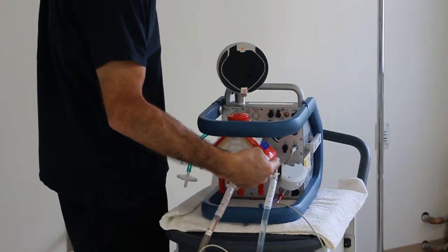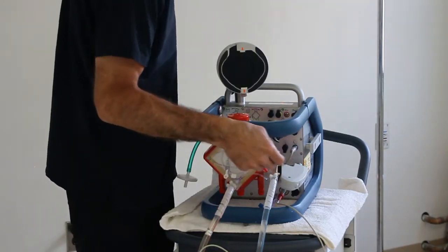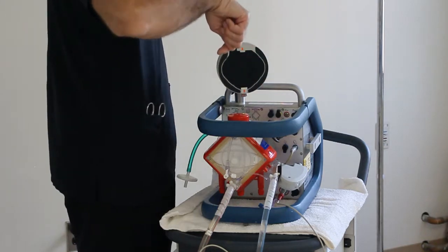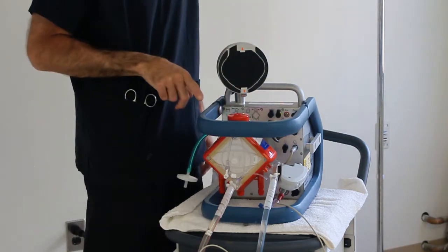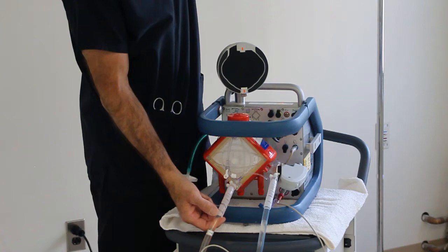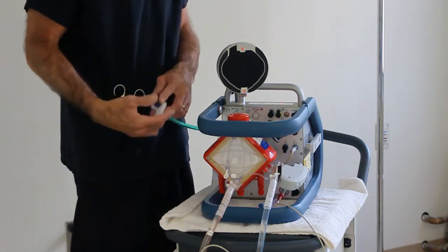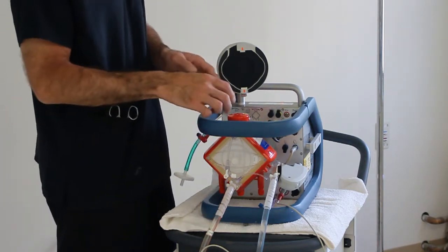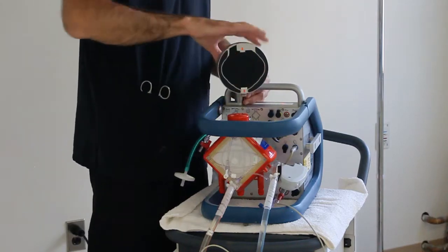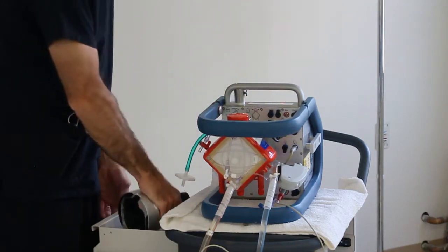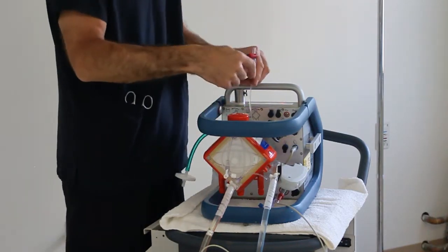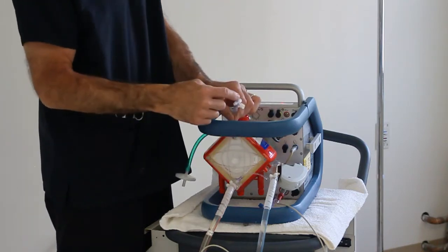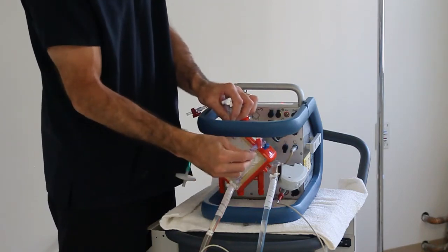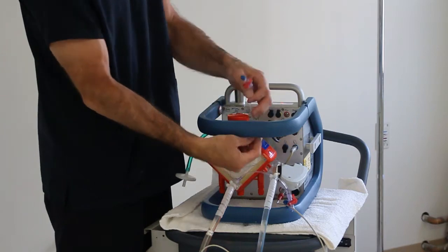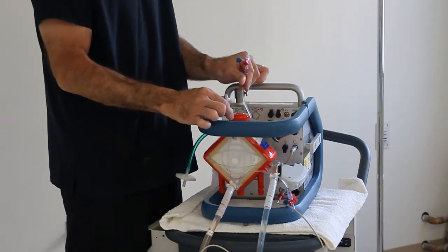We're draining fluid down the blue line. It's coming over right in here past the sat/crit monitor, going in and around through the pump and across the oxygenator in this direction, and comes out the other side. Now it's arterial blood. It's getting its gas over here. We have sampling here before the oxygenator. We have sampling after the oxygenator, and again after the oxygenator over here. These two are often used for crisis management.